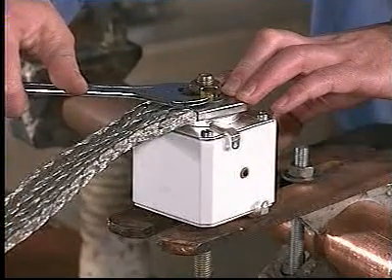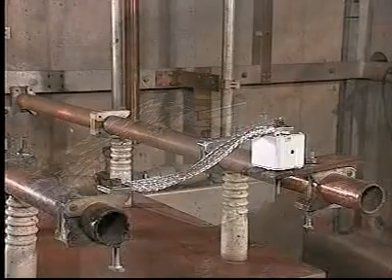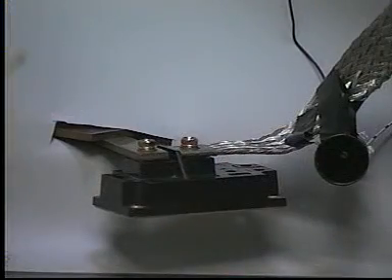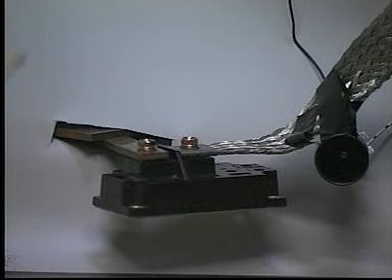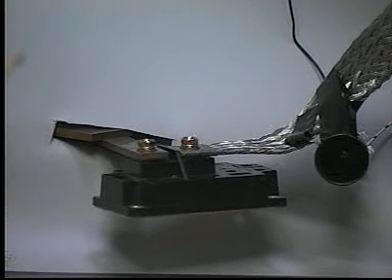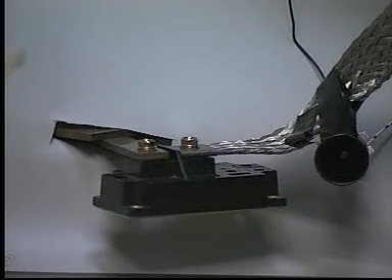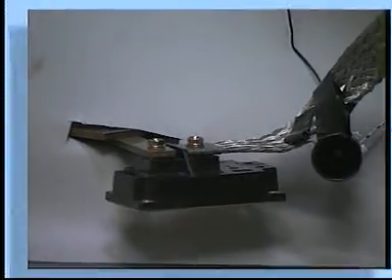The second test shows the same circuit conditions, with the only difference being the addition of an ultra-current-limiting semiconductor fuse. While the fuse is unable to protect the functionality of the IGBT, it is able to at least provide Type 1 protection, such that the ionized products are contained within the IGBT housing. In this way, adjacent circuit components are not exposed to explosive end-of-life scenarios.